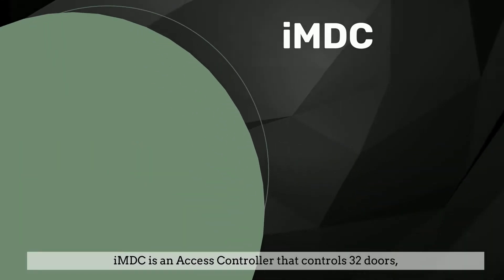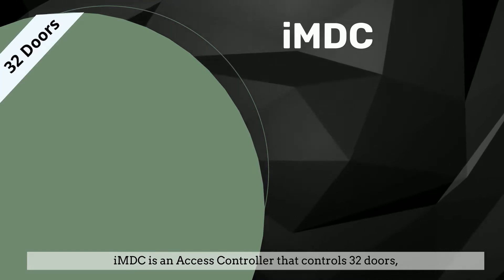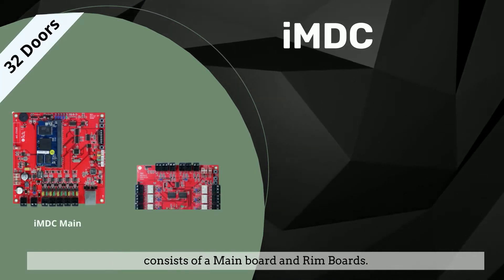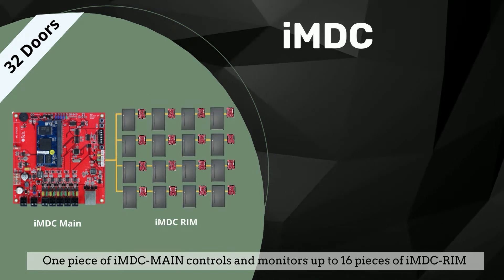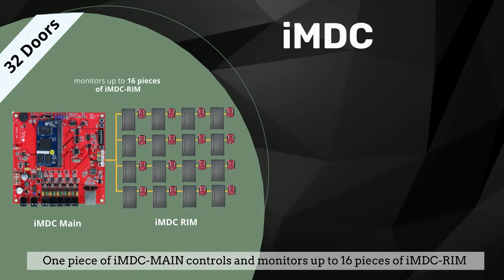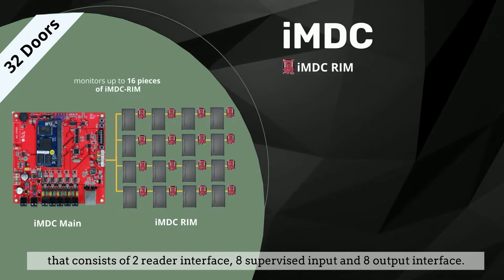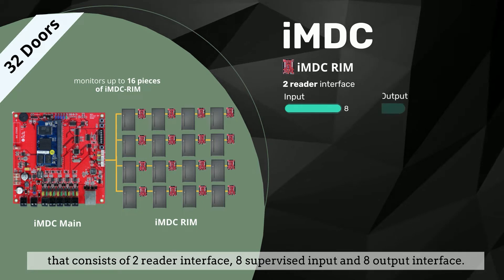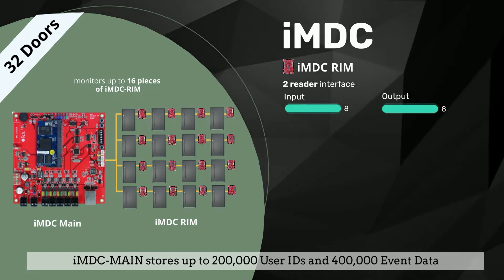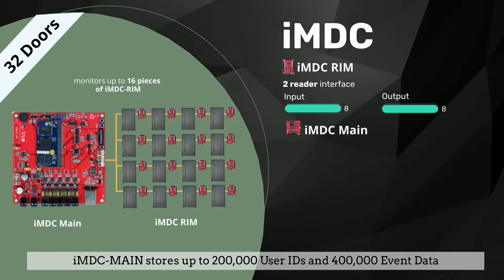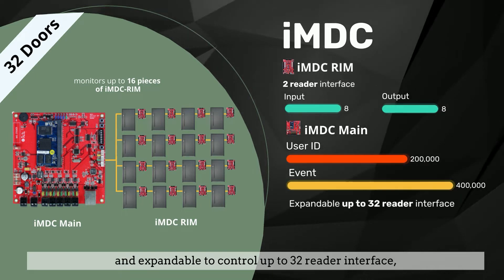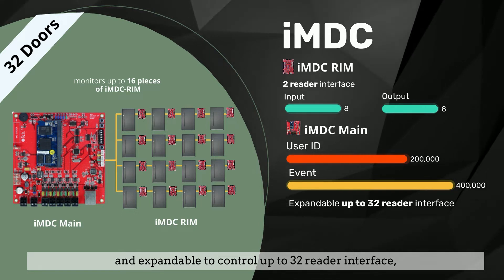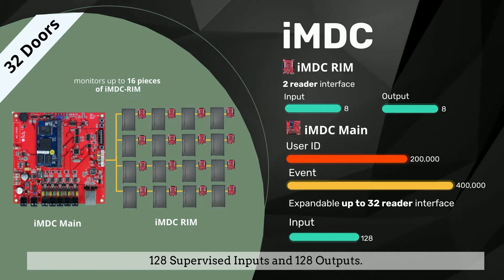IMDC is an access controller that controls 32 doors, consisting of a main board and rim boards. One piece of IMDC main controls and monitors up to 16 pieces of IMDC rim, each consisting of 2 reader interfaces, 8 supervised inputs, and 8 output interfaces. IMDC main stores up to 200,000 user IDs and 400,000 event data, and is expandable to control up to 32 reader interfaces, 128 supervised inputs, and 128 outputs.